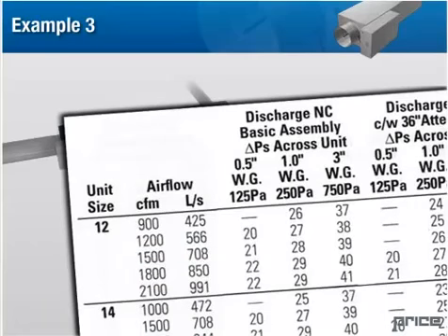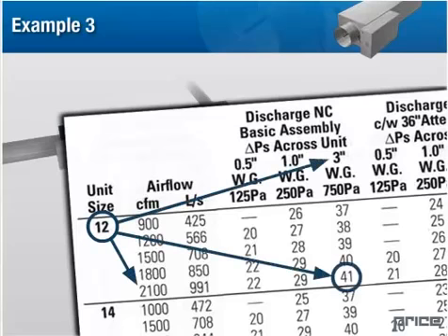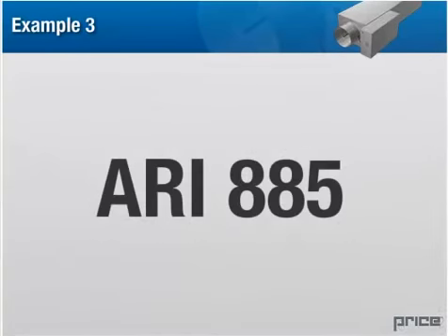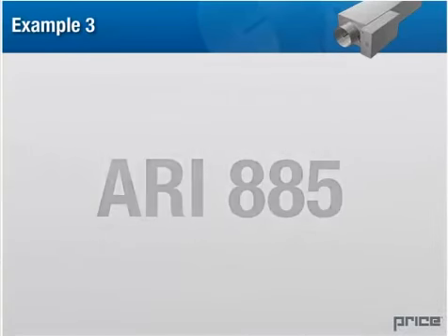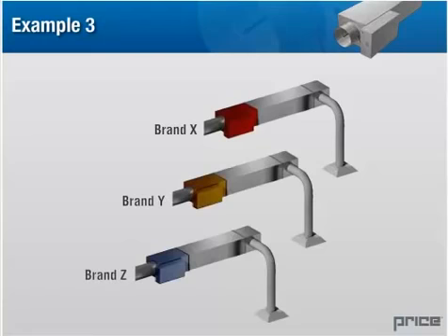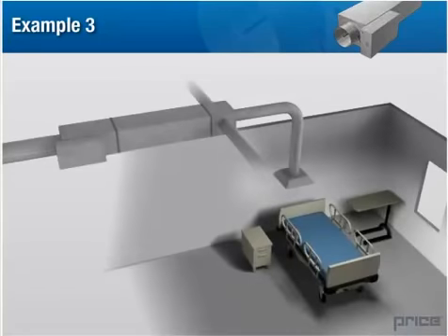By changing the terminal liner type and eliminating line ductwork, we have a resultant NC of 41. The deduction for line ductwork found in the ARI 885 deductions is not applicable to our project. While ARI 885 is a good standard for common applications and useful for comparing products, you should be aware of the assumptions involved when designing for specific applications.